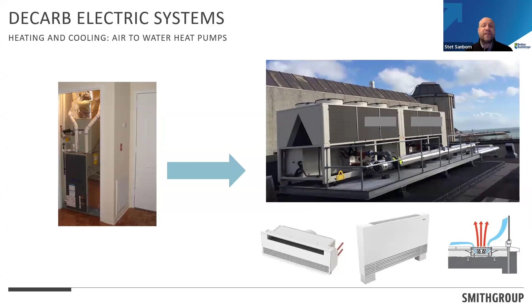Before you go buy a heat pump for your project, and before you look at a boiler and just buy a heat pump of the same size, we really, really encourage you to update or fix your hot water distribution and recirc system. There's a ton of energy waste from poorly designed or poorly operating recirculation systems in multifamily buildings.